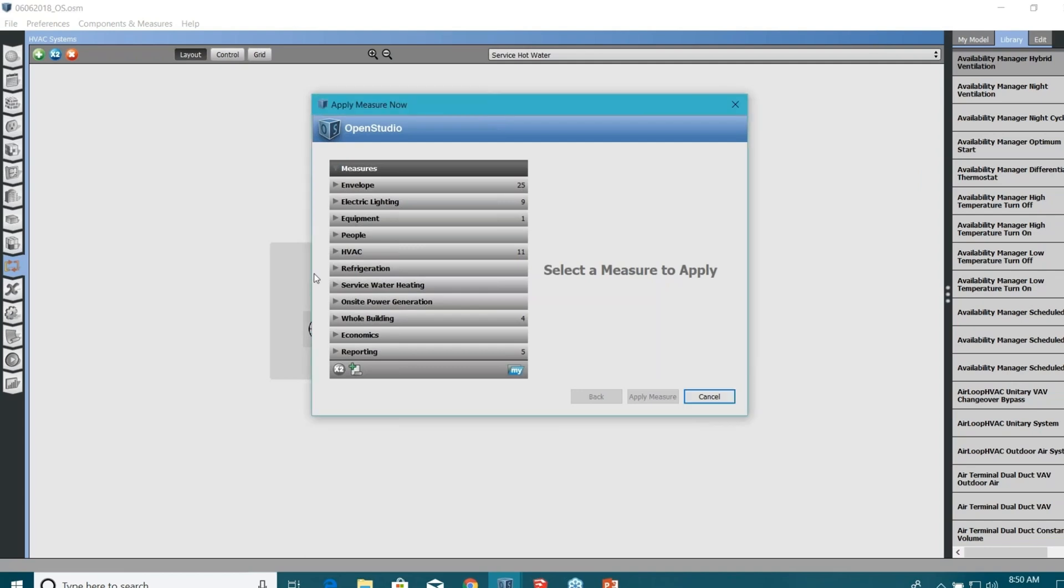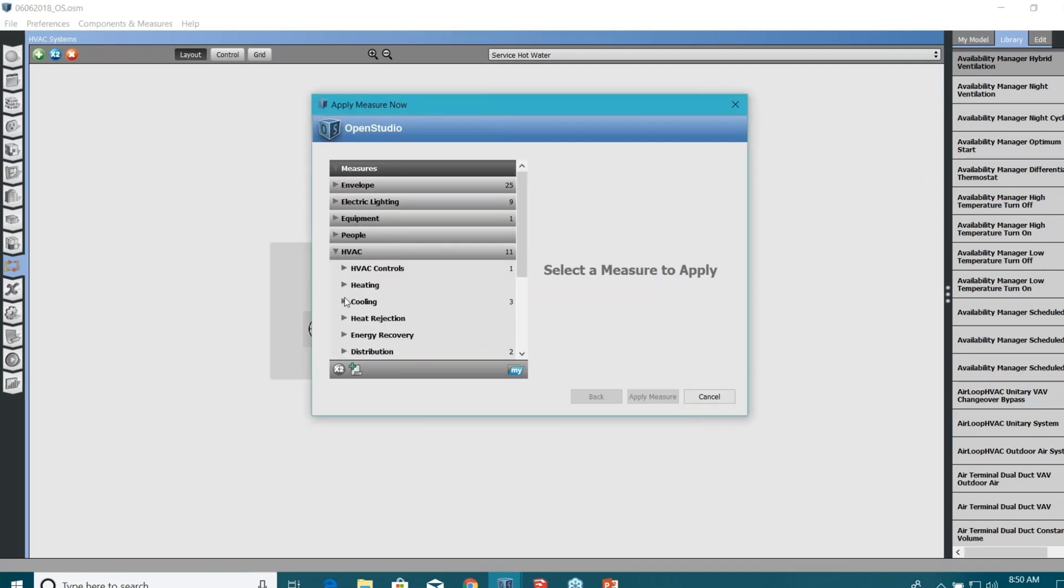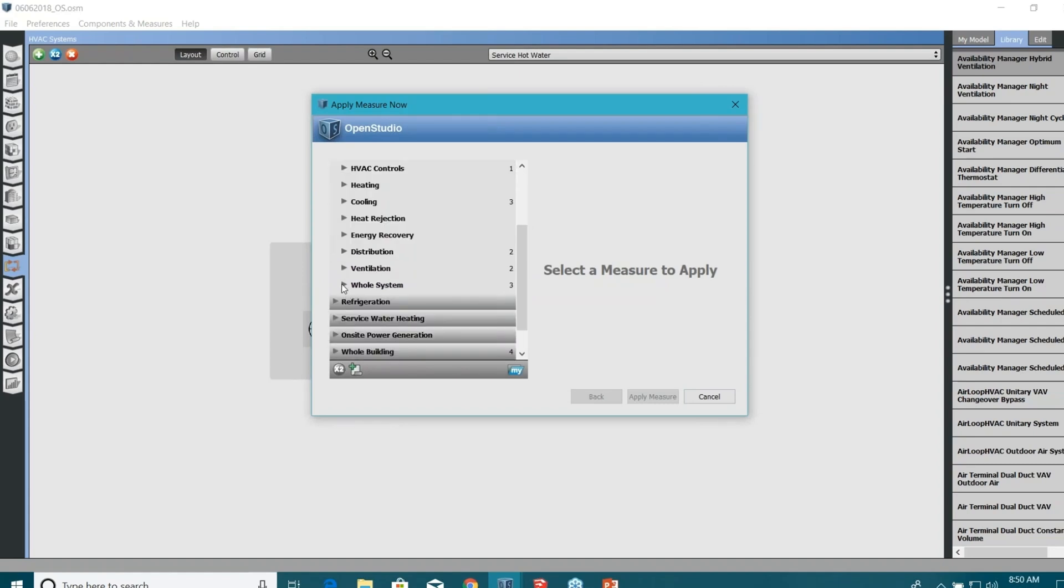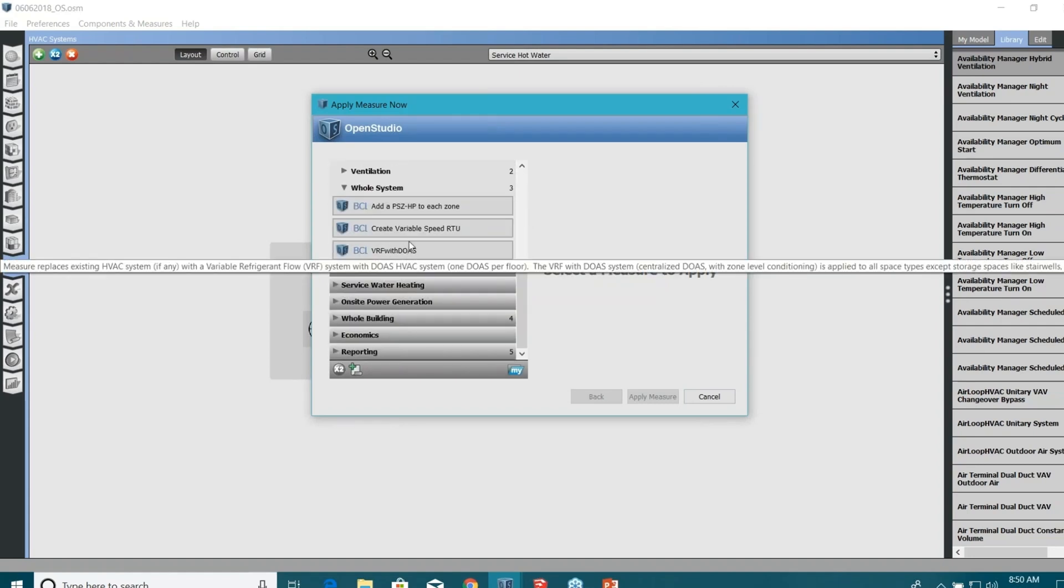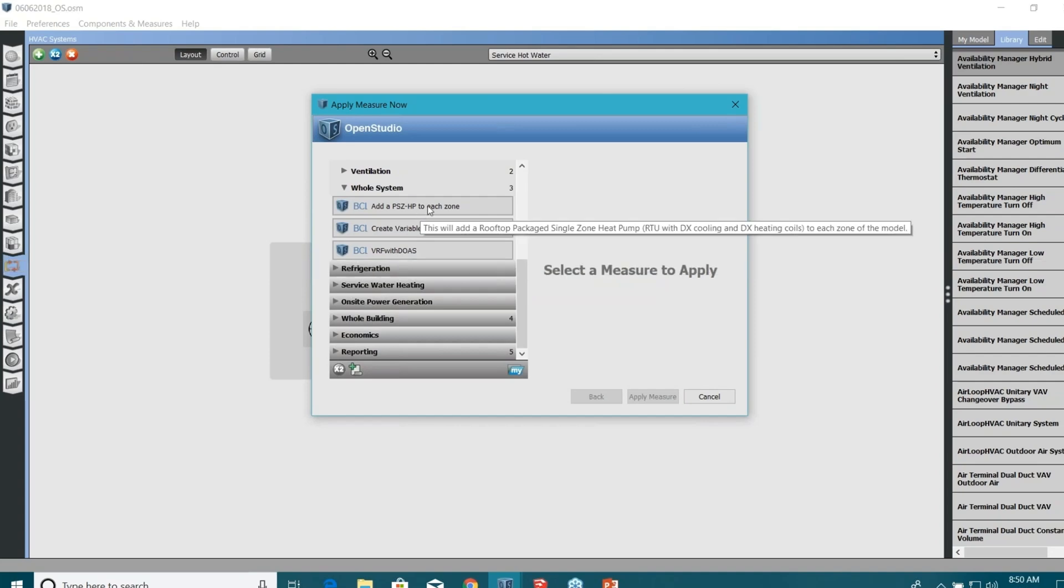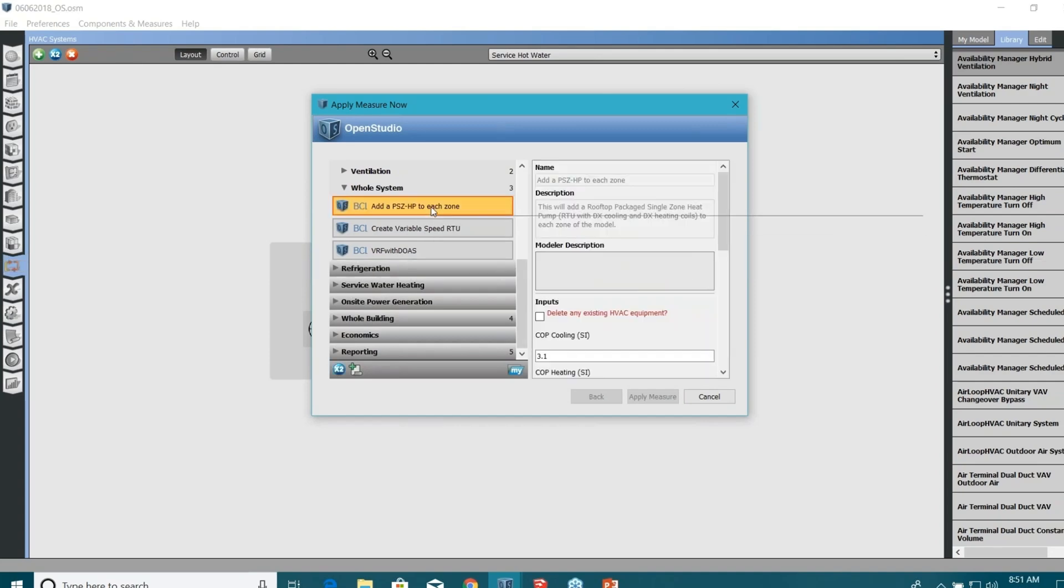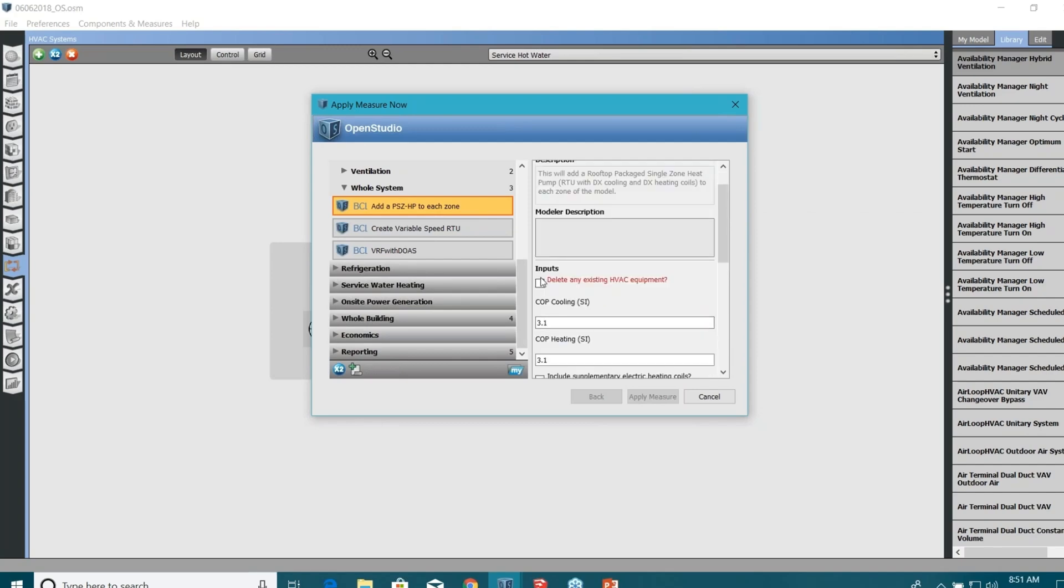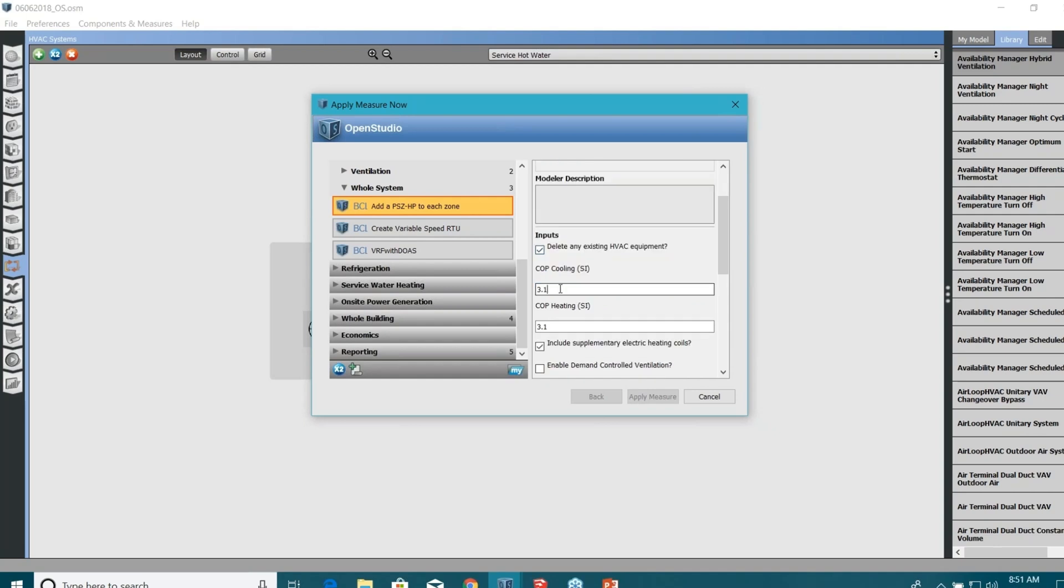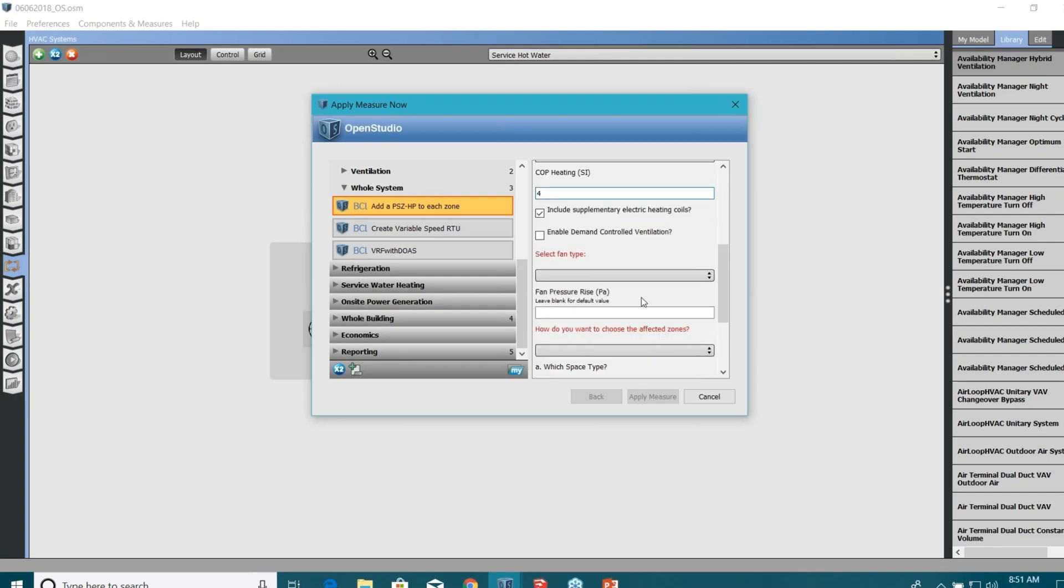I'm just going to run an HVAC measure here, which will be something like, let's say, VRF with DOAS. Okay, that's fine. Or maybe let's keep it simpler for now: packaged single zone heat pump to each zone. I'll do that. You can just tweak the properties. Okay, delete any existing HVAC component, COP for cooling, I'm just going to make it four, COP for heating four. These are very minimalistic property changes that you can do in OpenStudio measure, but you can make more changes later and I'll show you once we are done with this measure thing. Enable demand control ventilation, maybe yes.